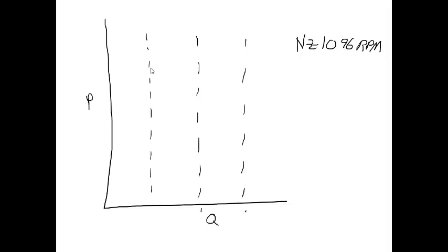I would have here, this would correspond to 1200 CFM. This would correspond to 1420 CFM. This would correspond to 1560 CFM. I have here my total pressure of 0.93 at 1200 CFM, and then static pressure of 0.75. Again, the difference between these two would be the velocity pressure, because that would be total pressure and that would be static pressure.